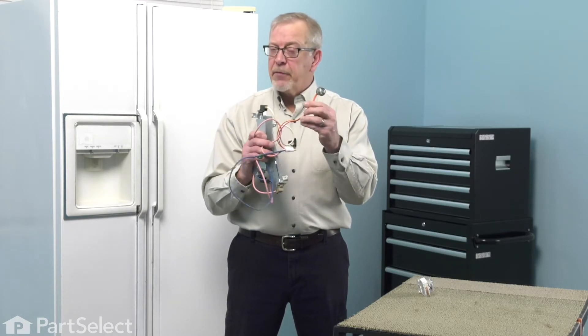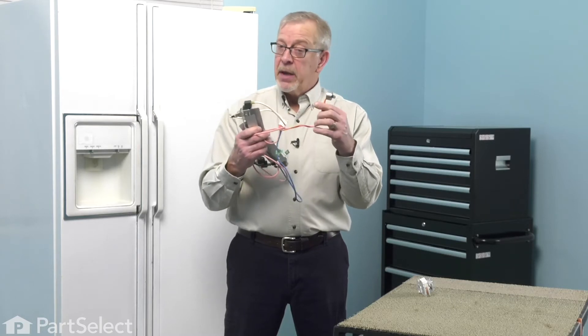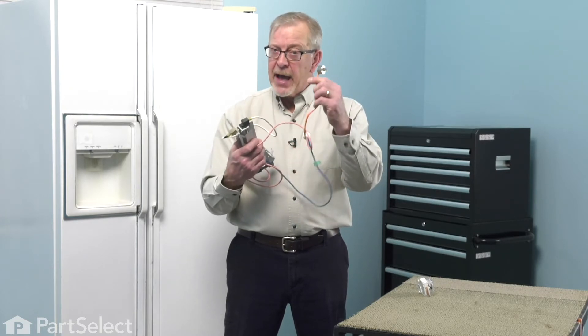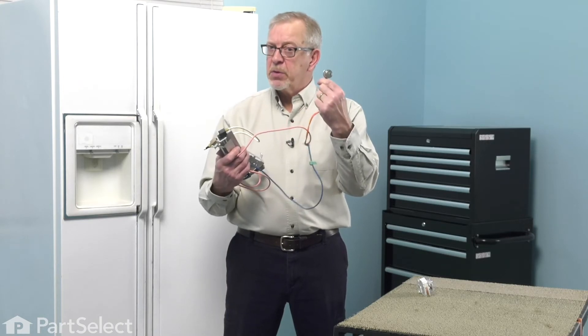At freezing temperatures, that defrost thermostat should show continuity. That may prove difficult to check if your refrigerator is not working properly, or if you've had to remove the evaporator cover to access it — it may have warmed up enough that it makes it difficult to test whether it is good or not.